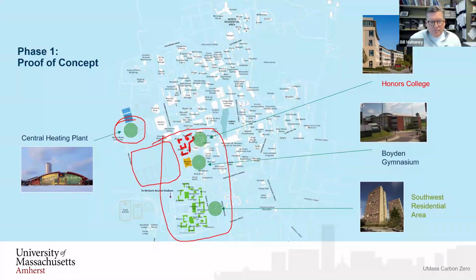Turns out it was actually kind of limited, not quite enough for us to do all the full load we needed to. Other problems with the areas that they selected here, there's an honors college, the red buildings, that's relatively new, heated and air conditioned, nice dorms. There was the Boyden gym, and there were a few other cats and dogs in there that were a couple of academic buildings, but very few. And then the majority of it was the Southwest resident area. It's these big, brutalist, 20-some story high-rise dorms, 1960s and 70s construction, bad windows, not much insulation, and no air conditioning.